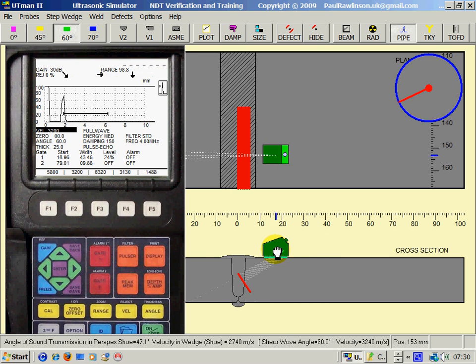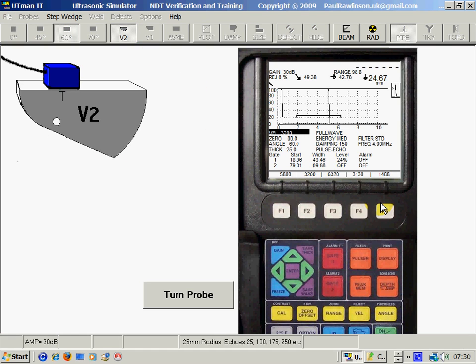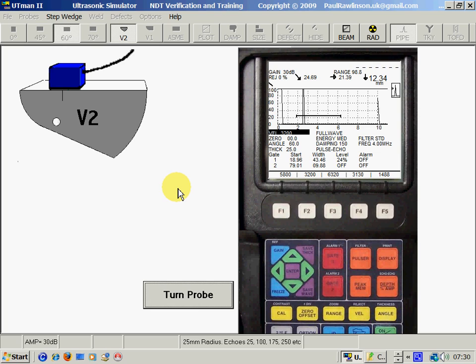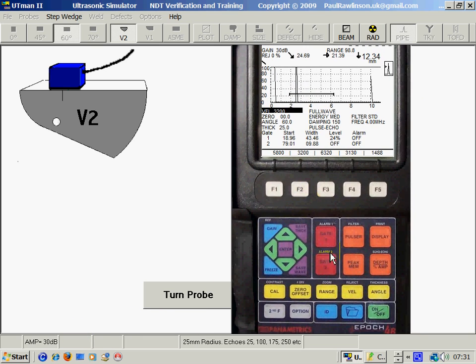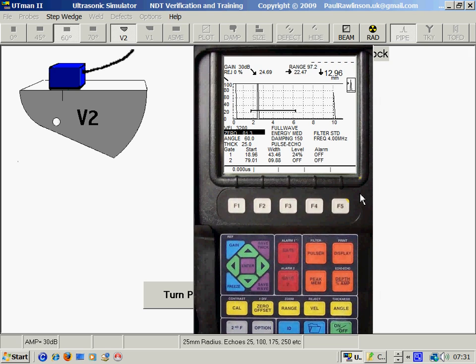Right, so to calibrate, let's put it on the V2 block. Turn it around to face the 25mm radius. Now, I'm going to click the range, move that slightly that way, and then increase the, actually I'm going to increase the range a bit, and then zero offset, move it back. And when you're on a graticule line, the front edge of the echo becomes dotted. So that's not a bad calibration. Turn the probe around, should be about the center, that's correct.